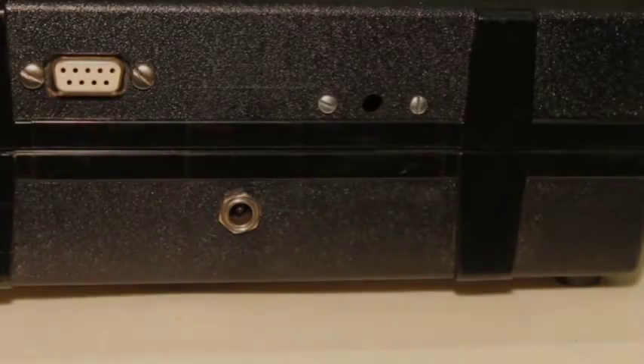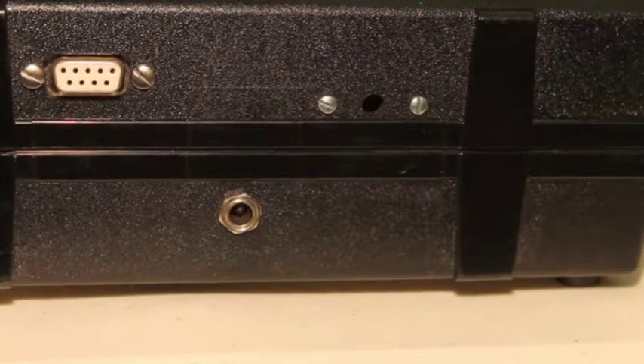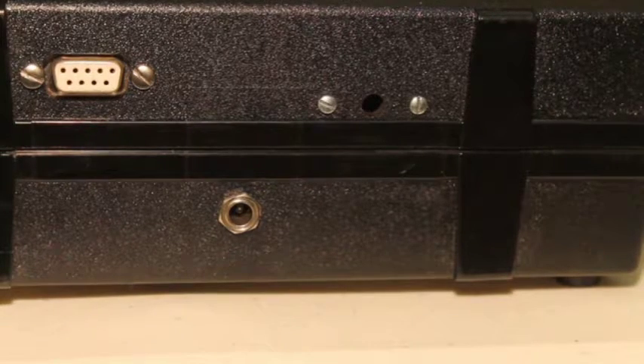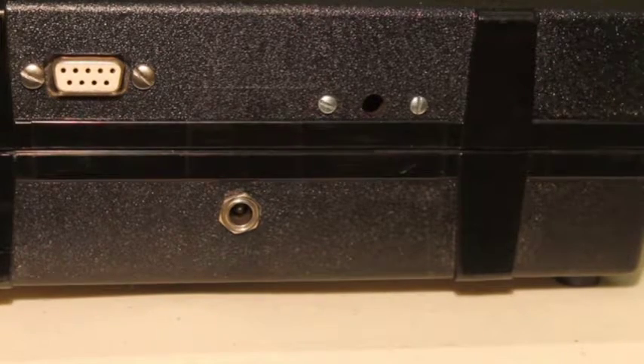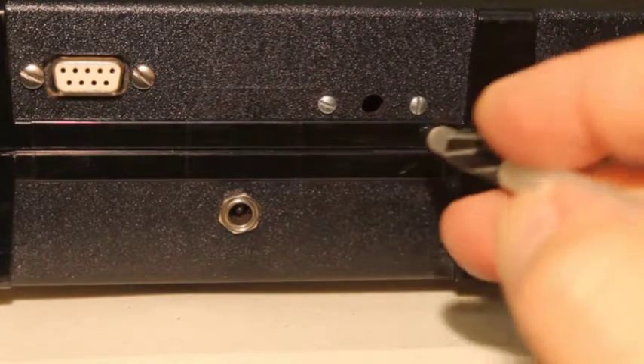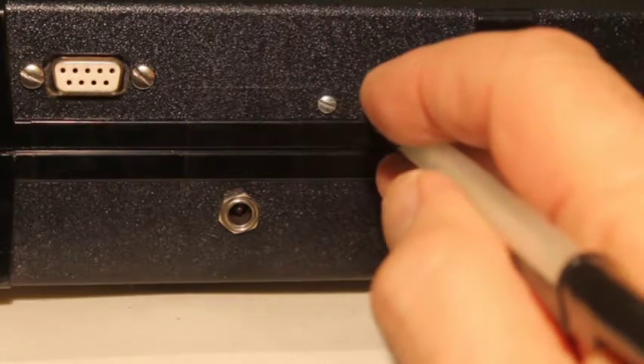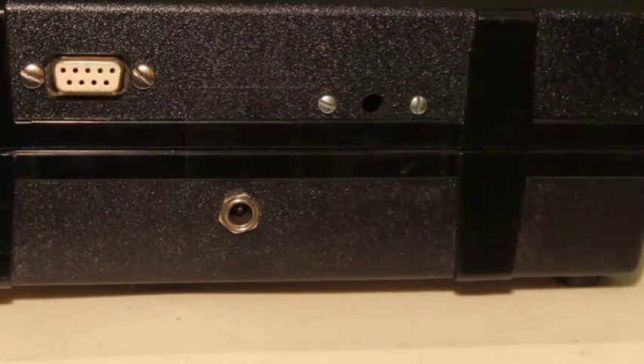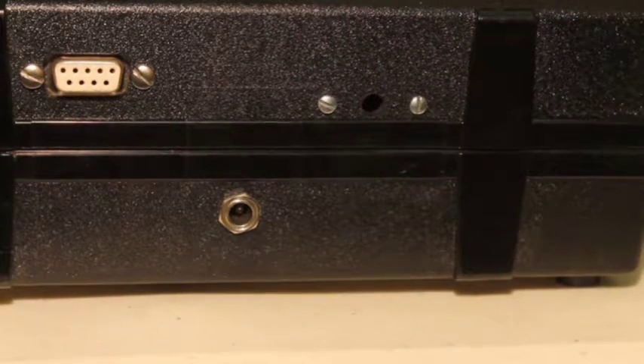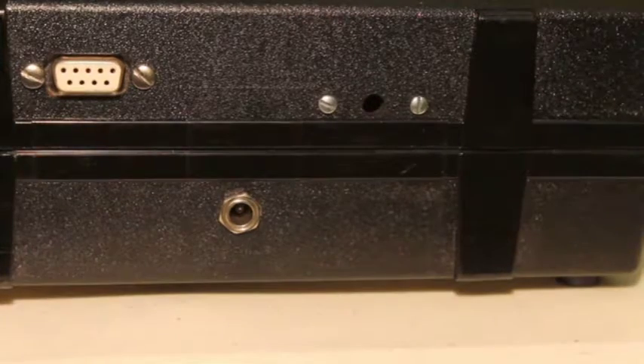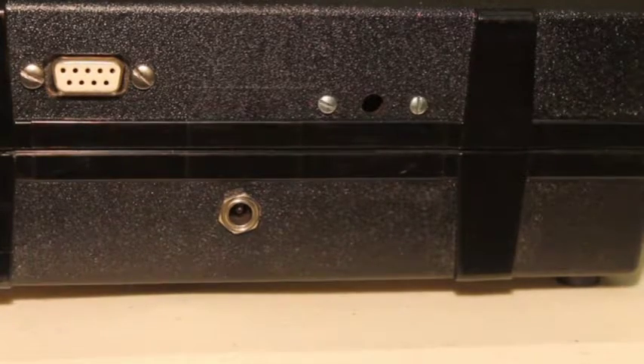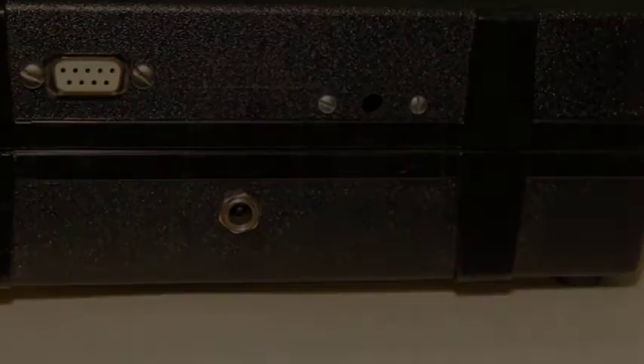On rare occasion, the instrument may appear hung up and none of the push buttons seem to have any effect. This happens when the batteries are very low and the instrument is turned on. There is enough energy to start the microprocessor, but not enough to complete the startup sequence. To remedy this, there is a small reset push button accessible from the rear of the instrument. With a pen or pencil, depress the push button switch. This action resets the microprocessor by disconnecting the battery. Charge up the instrument for a few hours and calibrate as normal.